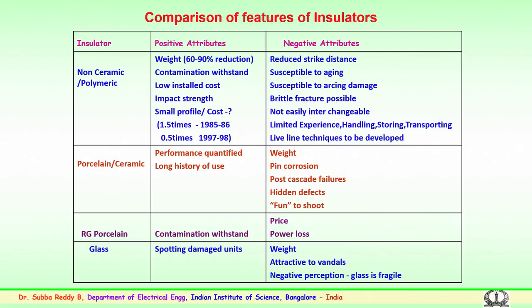Glass, like ceramic or porcelain, has the advantage that damaged units can easily be spotted because it is transparent in nature. Again, it is similar to ceramic or porcelain, where weight is one of the important criteria. As the voltage level increases, the number of insulators increases, and the weight also increases. Stringing is a concern, particularly at high altitude and in mountainous areas. Both porcelain and glass insulator stringing is a very difficult task. In particular areas they are attractive to vandals. Stone throwing and gunshots could damage the bells of the insulators and bring down the surface creepage of the string, causing failures. So, these are some of the comparisons of features of the various technologies being adopted.